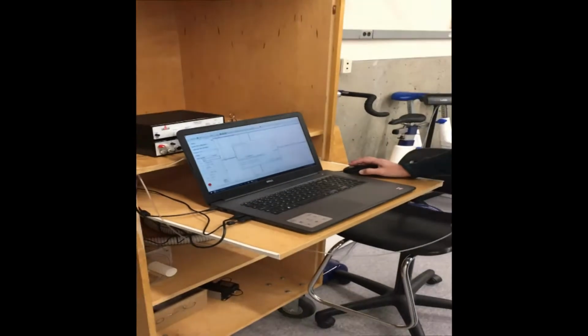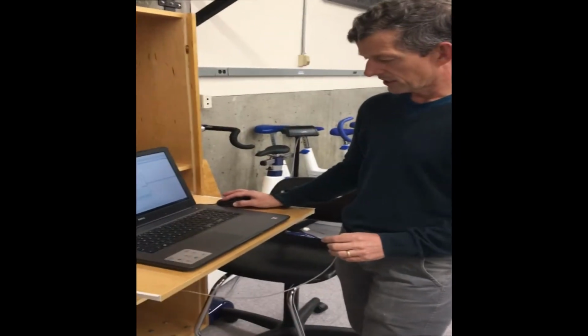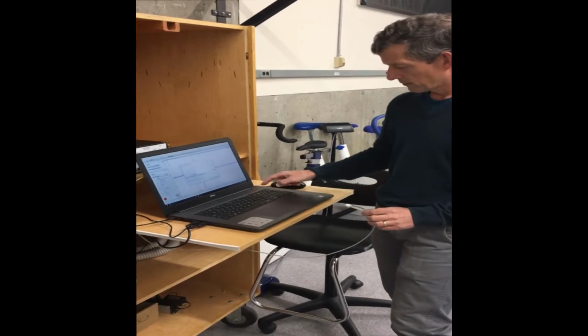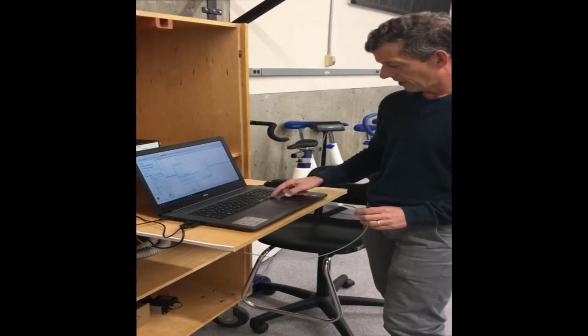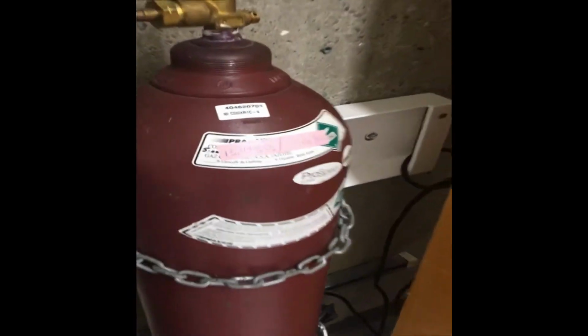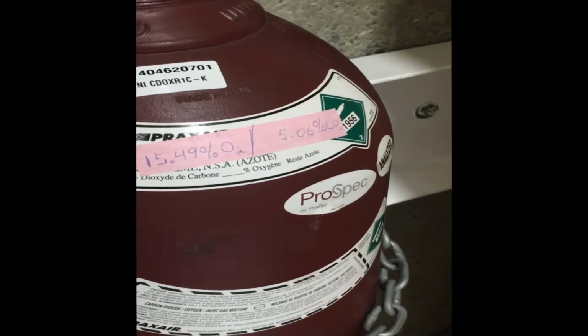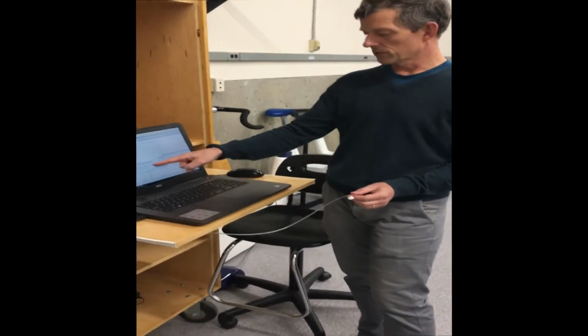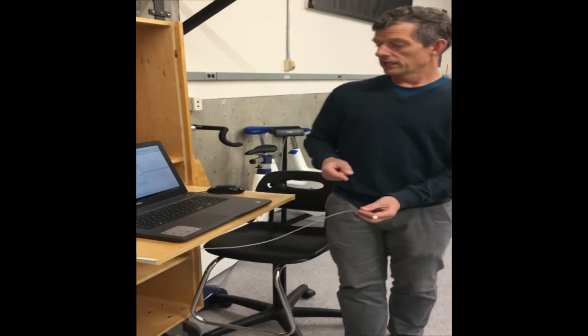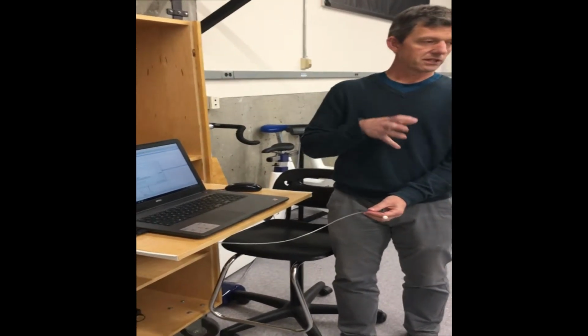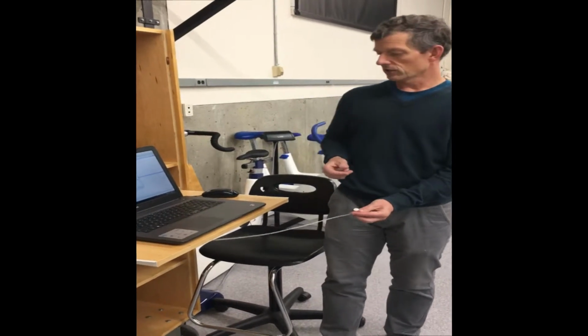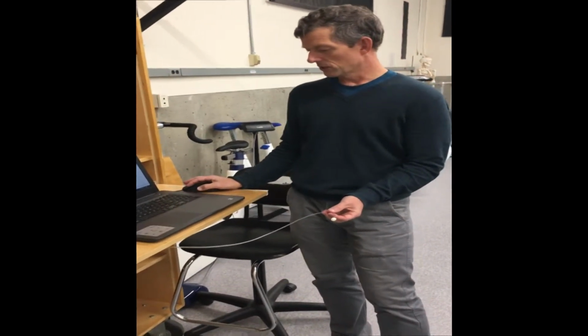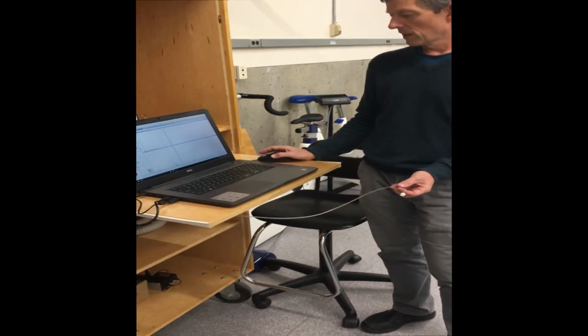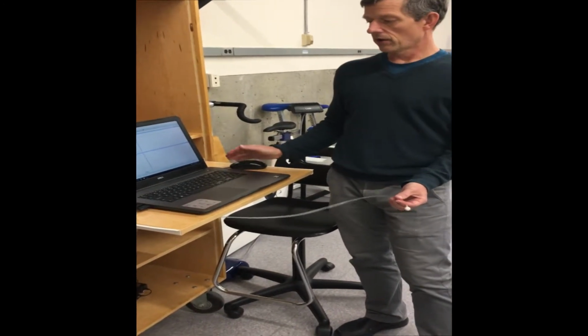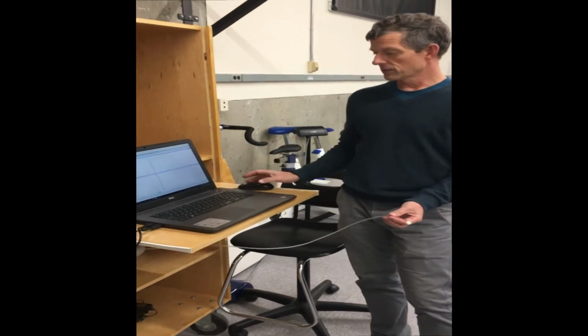Then the last thing that you need to do is put in what the calibration gas percentage was. So you're going to say that the calibration gas oxygen was 15.5%. And you're going to say that the CO2 is 5.06%. It's saying the room air is 20.93% and the CO2 is 0.04%. It does 0.04 instead of 0.03 because just us standing around, we're probably going to have an increase in CO2. So now all you need to do is click OK. And now it is ready to sample. And all you need to do to sample a gas is just click record.